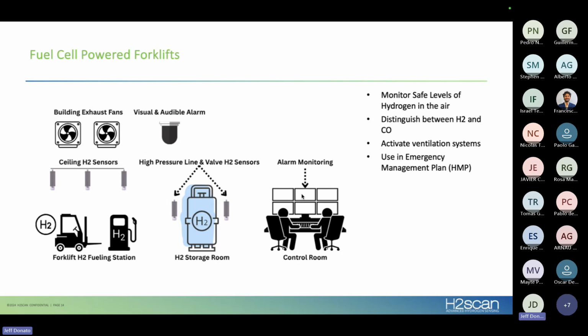One thing I will mention in both scenarios, and even in stationary battery applications, is that most hydrogen sensors have a cross sensitivity to CO or carbon monoxide, and most all carbon monoxide detectors are cross sensitive to hydrogen. And so if you have anything that produces hydrogen in an area, whether it be a battery system, a fuel cell, anything like this, and you're also having to measure for carbon monoxide, you're going to want to measure for both hydrogen and carbon monoxide so you can distinguish which is hydrogen and which is CO.